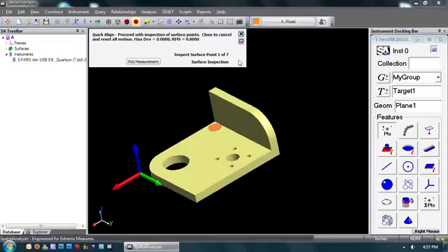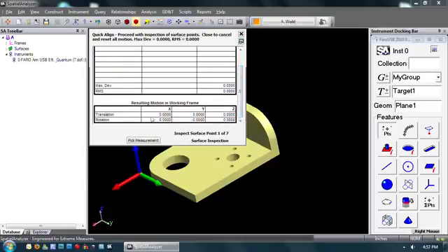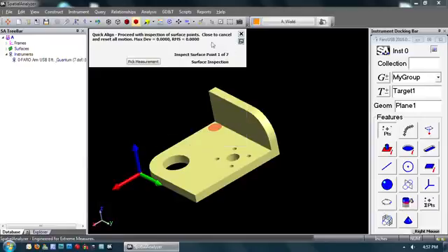The QuickAlign dialog will come up. This dialog can be expanded by clicking on this little window icon here, and this will show the details for your fit, including the max deviation, the RMS error, and also the transformation that's going to be applied from the fit. But when you're actually measuring, you can leave it collapsed in order to be able to see your view. Okay, before I measure, I'm going to set up my group. Let's measure this into a QuickAlign group, and let's give it a target name for the first measured target of P1.